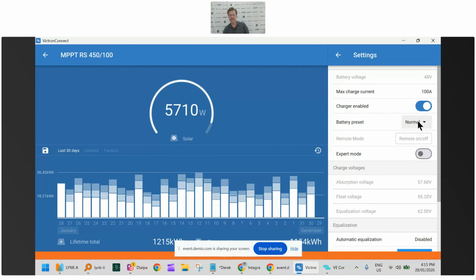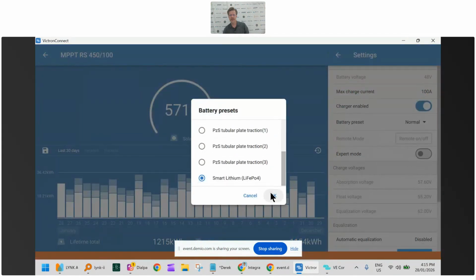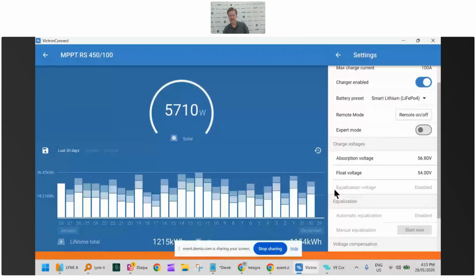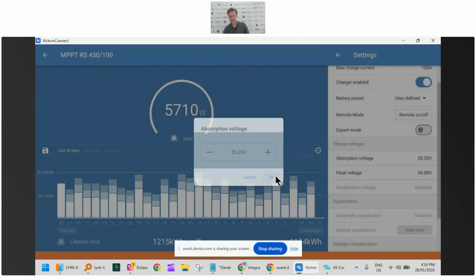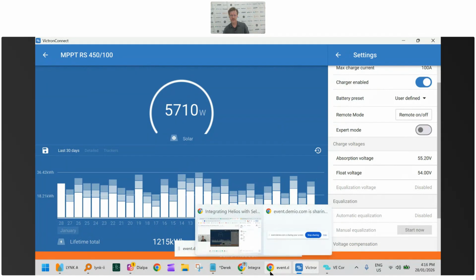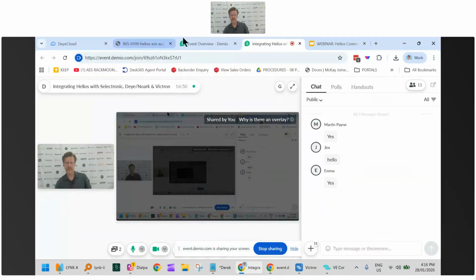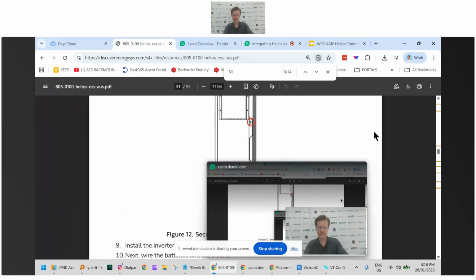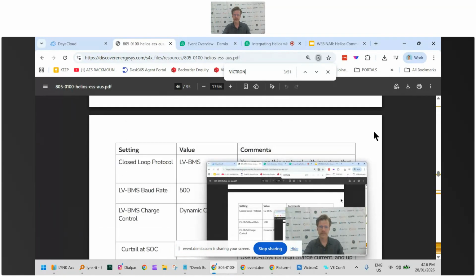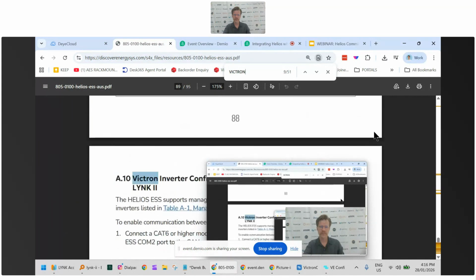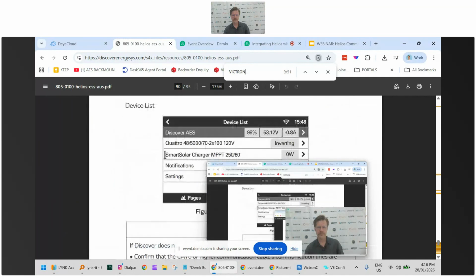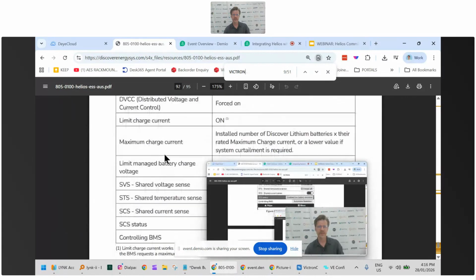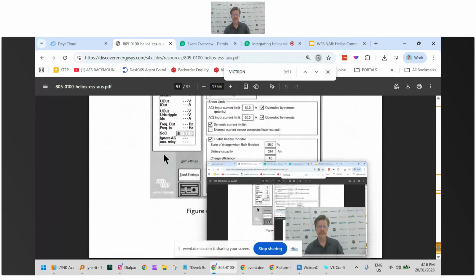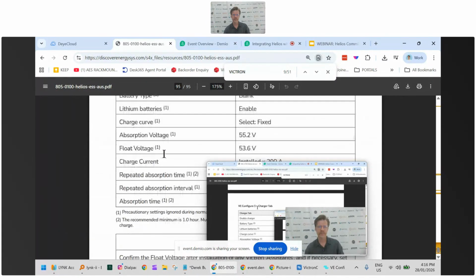The way I like to do this is I go in and select a preset, go down to Smart Lithium, and click OK - but I don't leave it on there, I just use it to set up the template. Then I'll go and change my absorption voltages to what is recommended in the Helios manual, 55.2, and we'll just check what they've got for the other value - 53.6, let's just check - yes, 53.6.